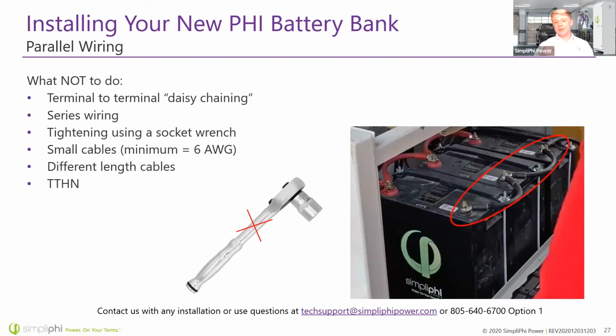So here's what not to do with your Phi batteries. Do not wire terminal to terminal. As you see here, this is common practice for lead acid batteries. However, it does result in imbalances in lithium batteries. Each of these batteries should have a direct connection to a common connection point instead of daisy chaining, as you see here. Don't wire them in series, of course, that is definitely going to cause damage. You cannot use two 24-volt batteries in series to create a 48-volt battery bank, at least not with Phi batteries.